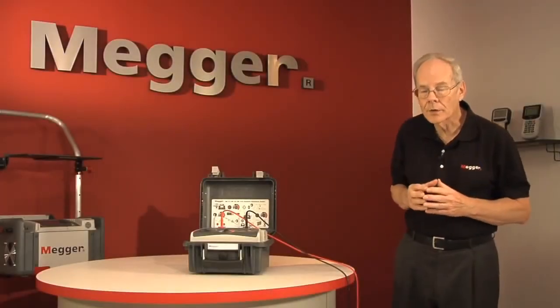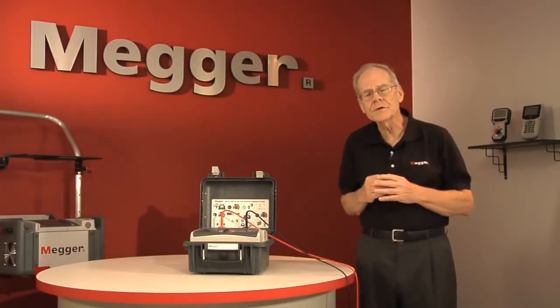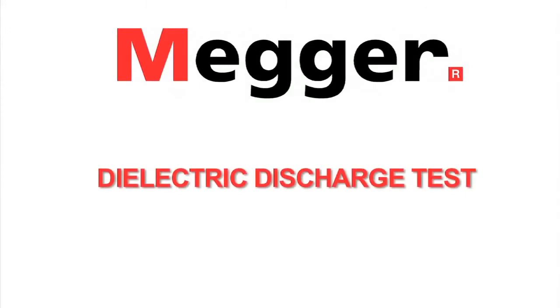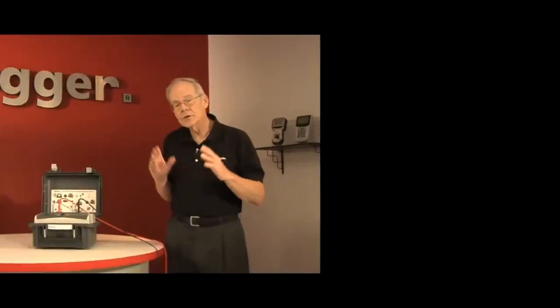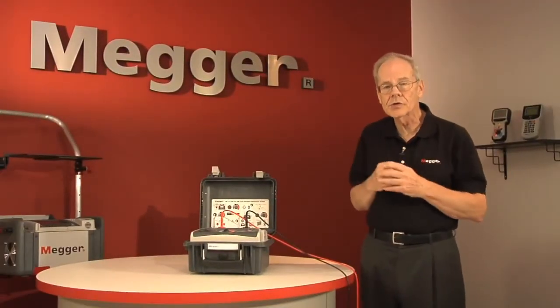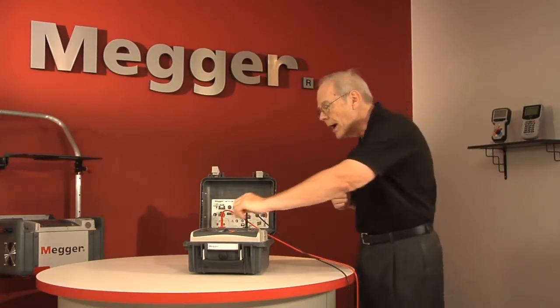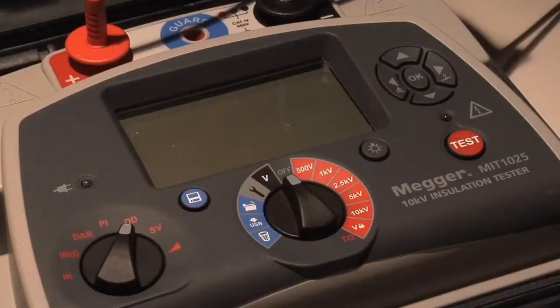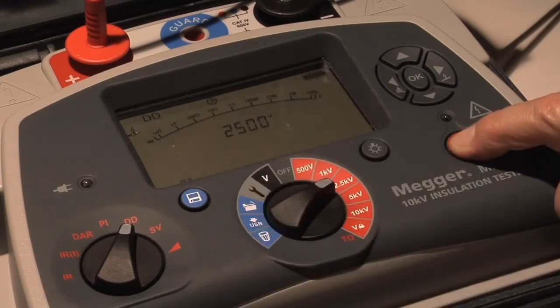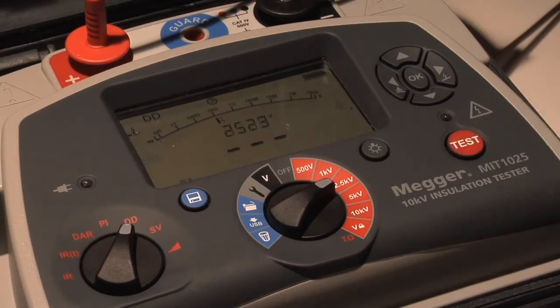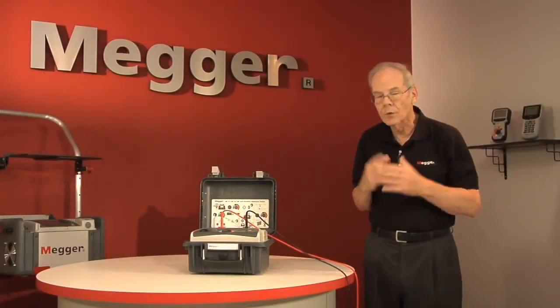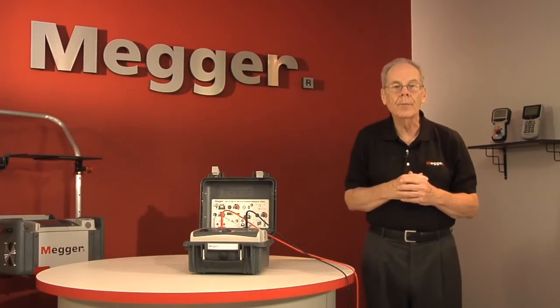And the final test we're going to look at is, again, another sophisticated test, the dielectric discharge test. Now this one is fully pre-programmed, so there's no setup to do. It's just a matter of a selector switch position, again, your test voltage and your test button, and the operator then steps aside, and this one is a very long test. It runs for 30 minutes, so you can schedule some other work to do while this is in operation.